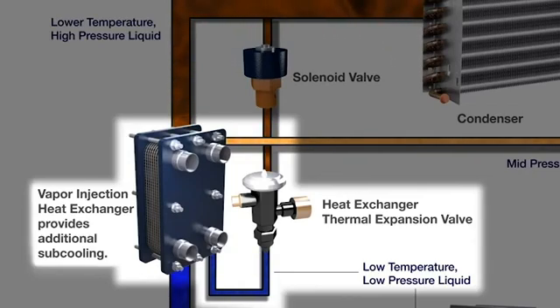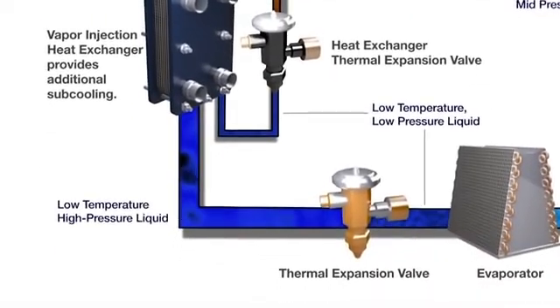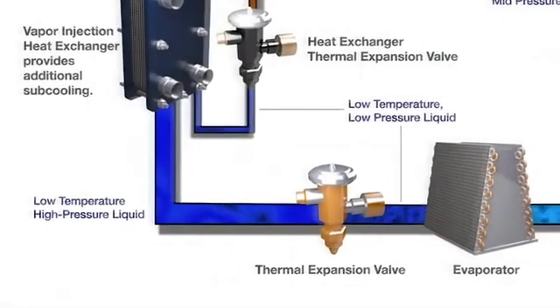The liquid in the main circuit also passes through this heat exchanger, where a portion of its heat is conducted to the vapor injection circuit. The liquid in the main circuit is sub-cooled, resulting in up to a 50% gain in capacity at 20% greater efficiency.